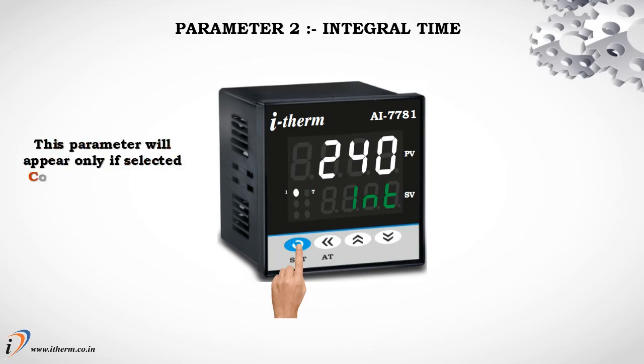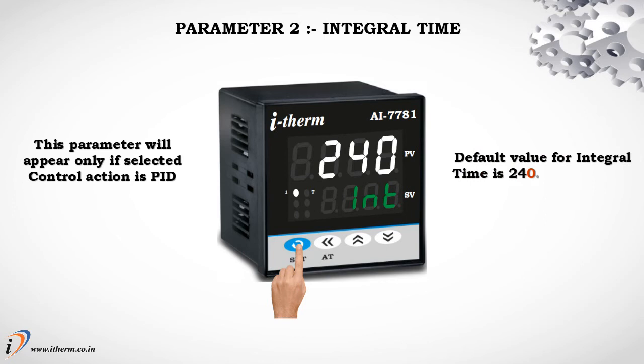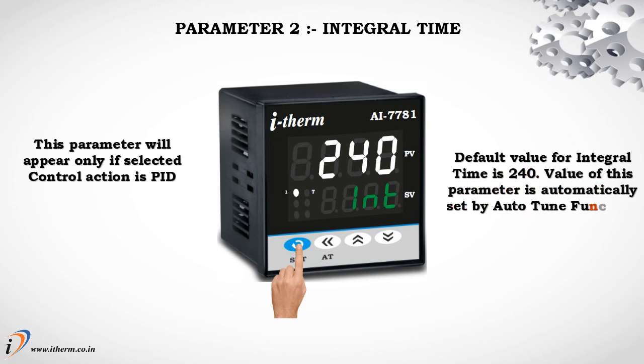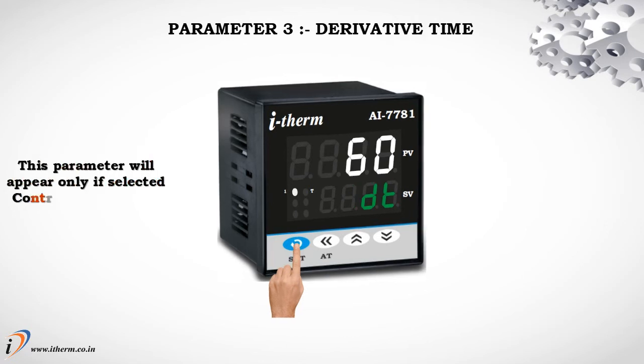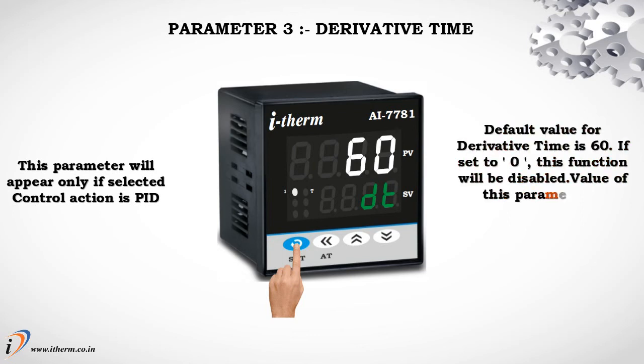Parameter 2 is Integral Time. This parameter will appear only if the selected control action is PID. The default value for integral time is 240, and it is automatically set by the Auto-Tune function. Parameter 3 is Derivative Time. This also appears only in PID mode. The default value is 60. If set to 0, this function will be disabled. Its value is also automatically set by the Auto-Tune function.